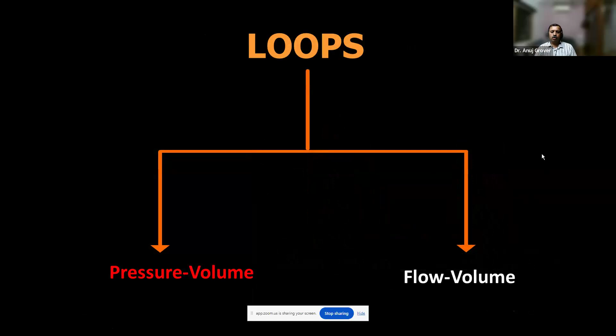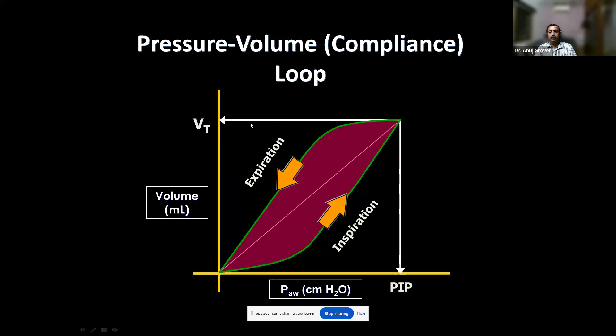We're coming to the two loops. The first is the pressure volume loop. This is one of the most important ones to look at. Here you have volume on the y-axis and pressure on the x-axis. During inspiration, this is how the hysteresis looks. The volume goes up with the increase in pressure, and during expiration it forms a loop. It doesn't go up and come down along a straight line; it forms a loop like this. This is your maximum PIP, and this is the tidal volume that has been achieved.